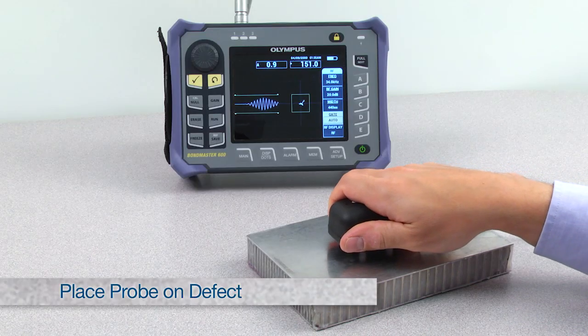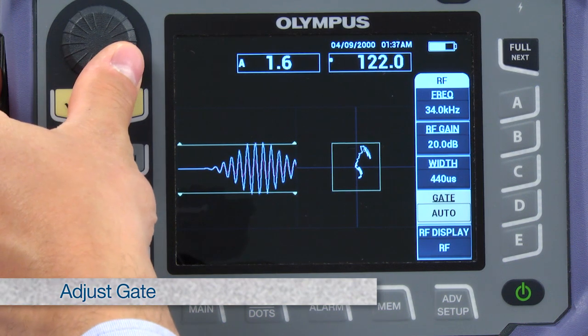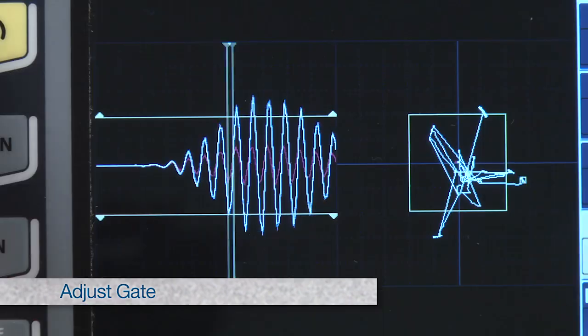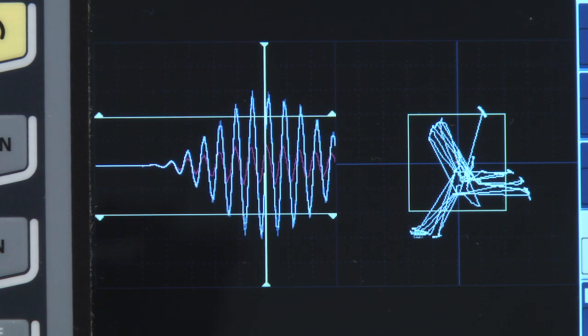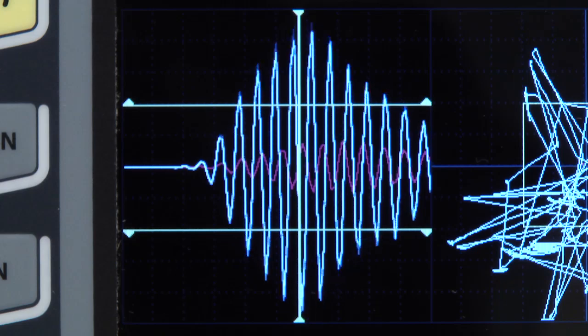Move the probe over the defect and hold it there. Using the knob, adjust the gate. Locate the position where the disbond signal amplitude differs the most from the reference signal. This is normally at the signal peak.